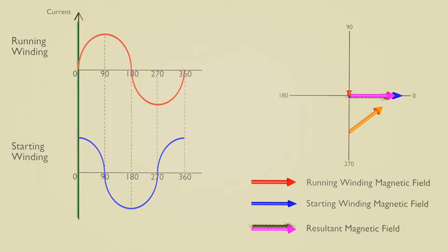At zero degrees, the current in running winding is zero but current in starting winding is maximum, so the resultant magnetic field is at zero degrees. At 45 degrees, the current in running winding is average and current in starting winding is average, so the resultant magnetic field is at 45 degrees. At 90 degrees, the current in running winding is maximum but current in starting winding is zero, so the resultant magnetic field is at 90 degrees.